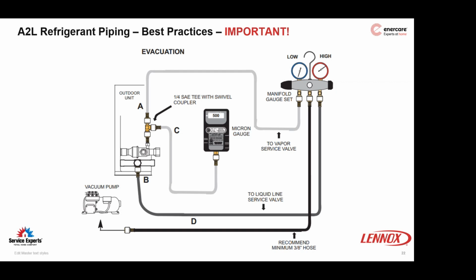However, if after 10 minutes the reading is between 1,000 and 2,000 microns, you're going to have to do a nitrogen sweep to relieve that system of whatever moisture is still hanging out, and then relieve that pressure from the nitrogen and start your evacuation all over again. And then, of course, if by chance your vacuum test exceeds 2,000 microns within that 10-minute test, there's likely a leak somewhere in the system, and the pressure test didn't reveal it. So maybe go around and see if you can isolate where your leak is coming from. Who knows? It could very well be coming from a hose connection.